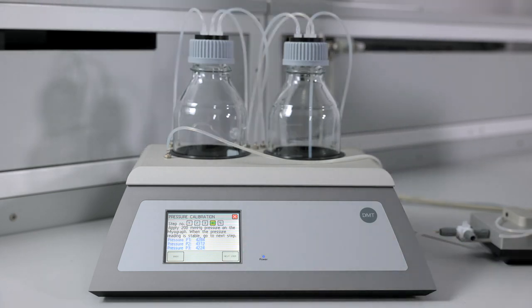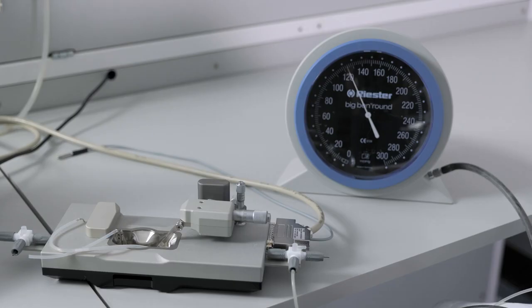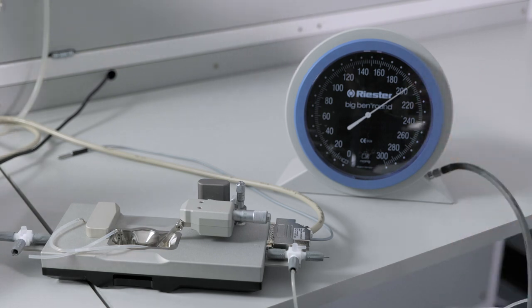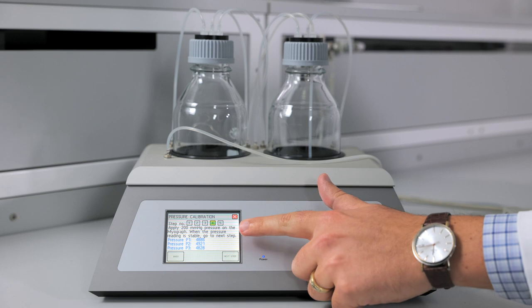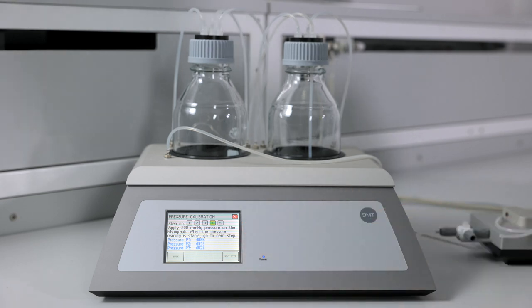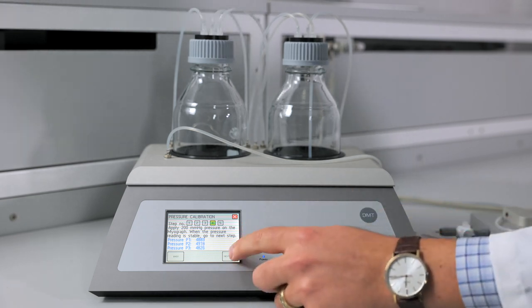The final step is 200 millimeters of mercury. Be cautious not to go too high, as the transducers can blow once you bypass 250 millimeters of mercury. So we increase to 200. Pressure is holding again. You can see our pressure readings have all increased again. We can hit next step.